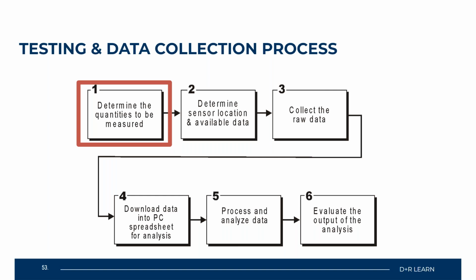physical logs. So have your day-to-days that run around and do the dailies, have them log everything every day, what the temperature, supply and return temperatures were, what the velocity of air was coming out of the air handler, any delta T's that need to be measured, water pressure, whatever. Have everything logged every day in a manual logbook. And then if you still have those capabilities at the end of the day or throughout the day, have those technicians provide that data to your data entry personnel that works your BAS system.